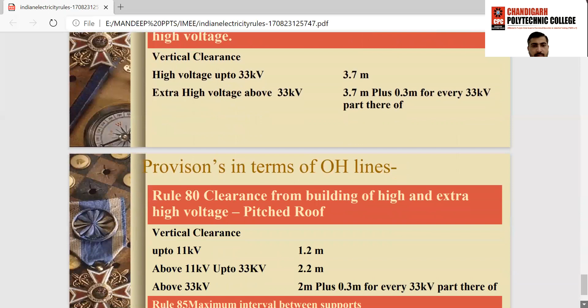Under Rule 80, the clearance from building of high and extra high voltage of pitched roof type. The vertical clearance required up to 11 kV is 1.2 meter. Above 11 kV up to 33 kV, the clearance required is 2.2 meter. Remember, it is for pitched roof. And above 33 kV, the minimum clearance required is 2 meter plus 0.3 meter for every 33 kV or part thereof. It means if we use a 66 kV line, the minimum clearance from the pitched roof required is 2.3 meter: 2 meter plus 0.3 meter added.